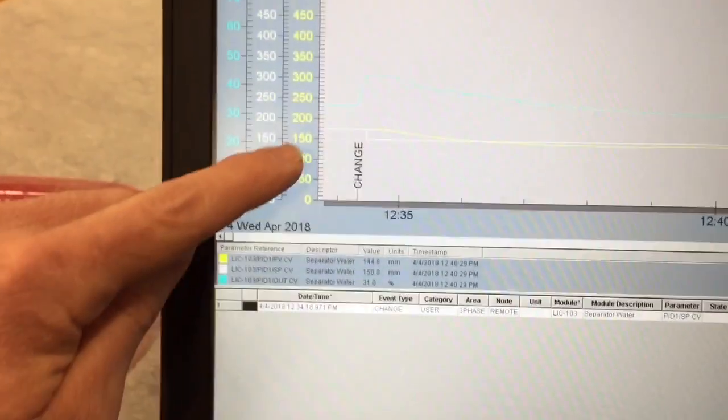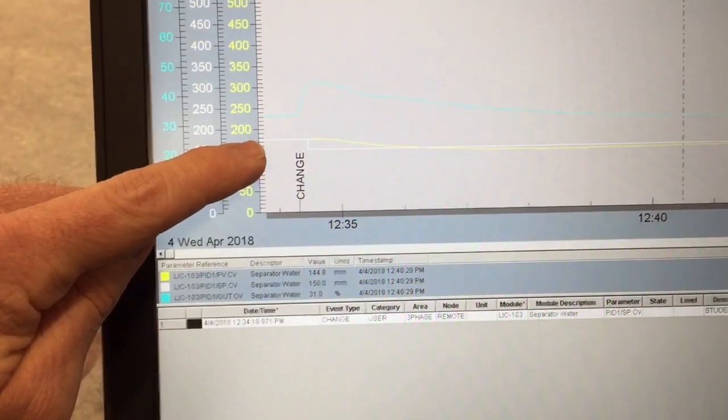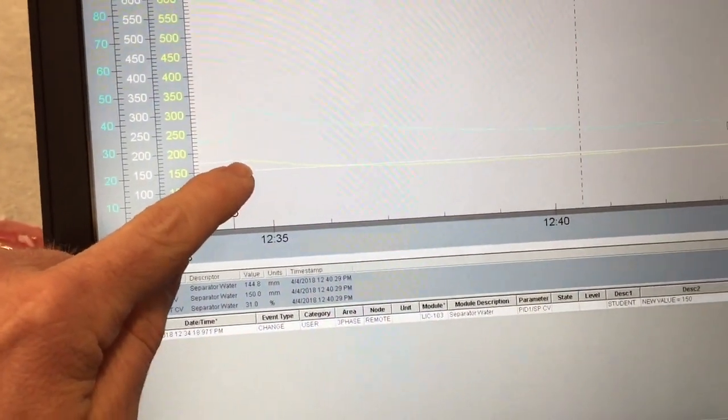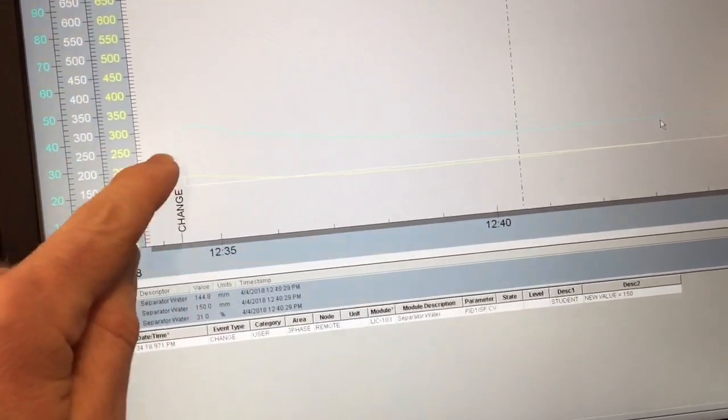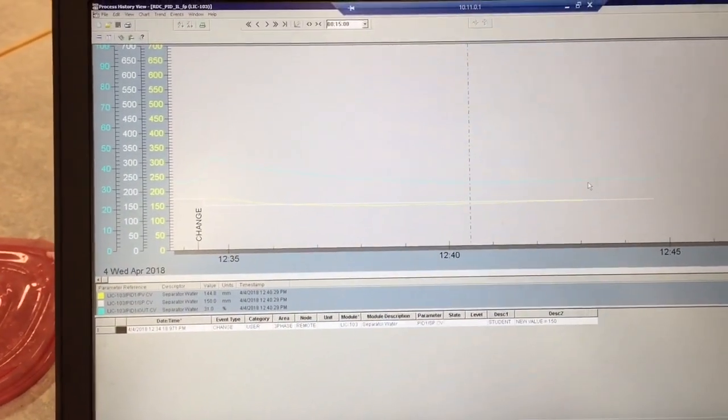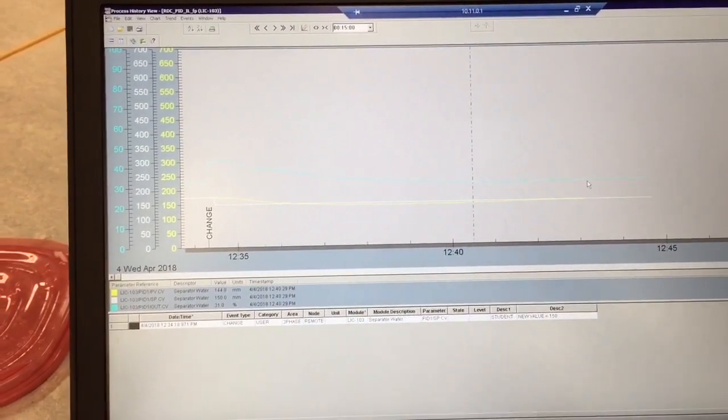So you can see we made our step change from 175 millimeters down to 150 right here. And the interface level came down. This is our controller output here, came down to eventually match the set point. So it appears we have our interface level controller tuned up quite well.